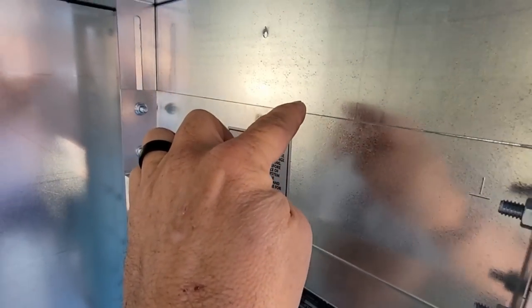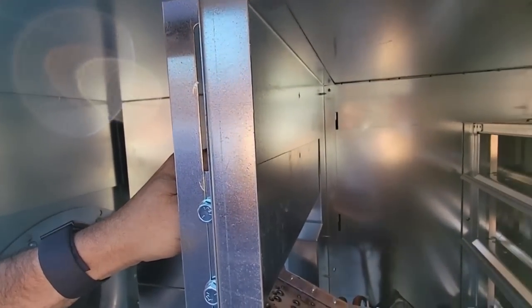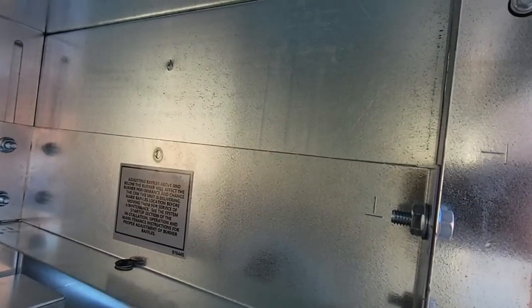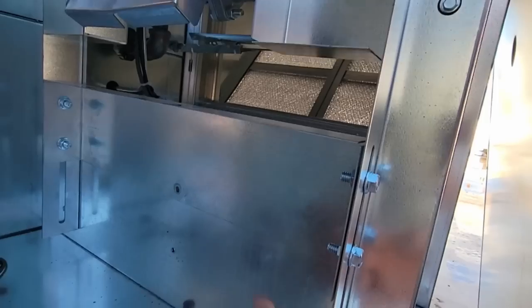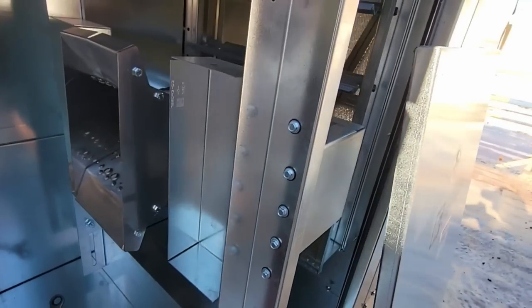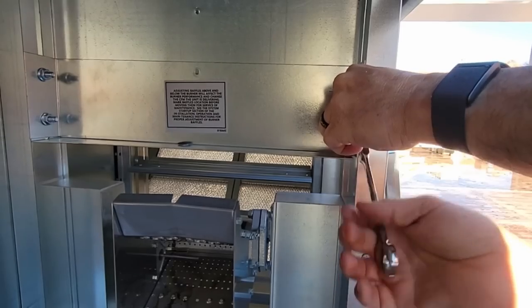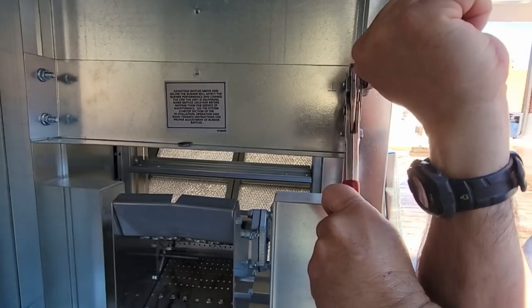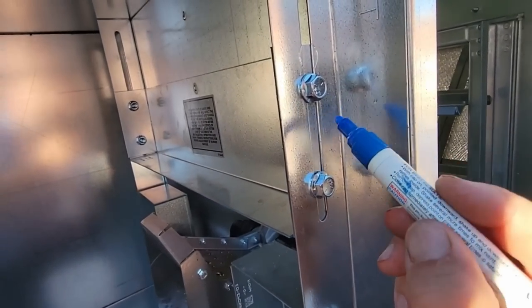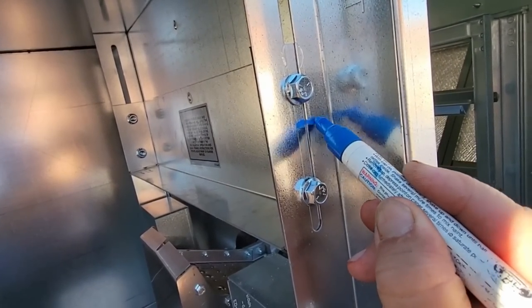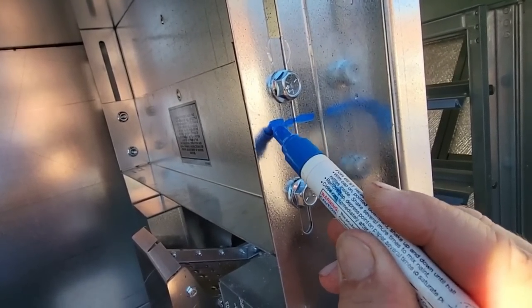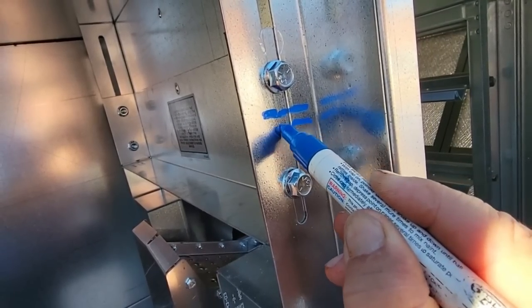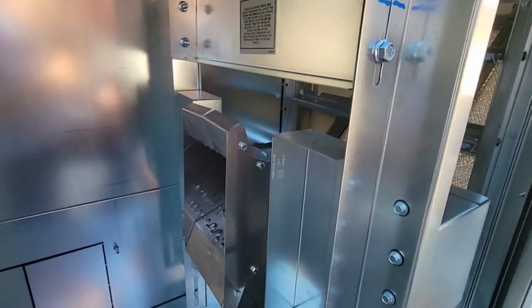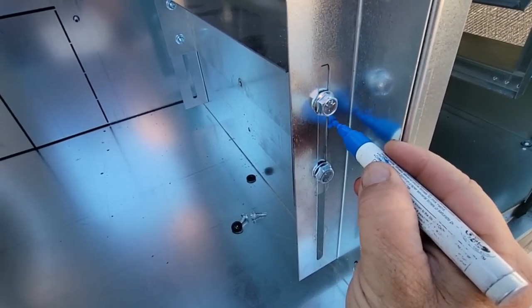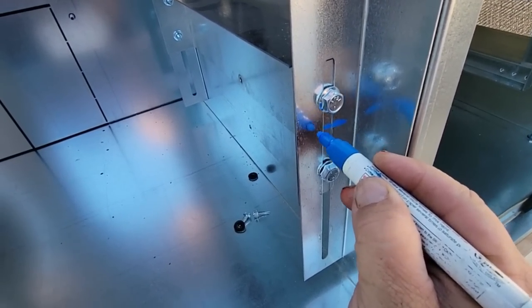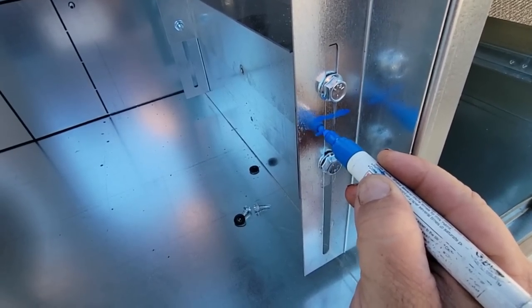As you can see, we are just barely covering that so that there's not leakage at the top. I mean, there's no daylight. Same thing with down here. So we'll go ahead and tighten that up. Go ahead and mark this where we had it at. That way, if somebody screws with it later, we can prove that we had it where it belonged at the frequency that it was running at the time.